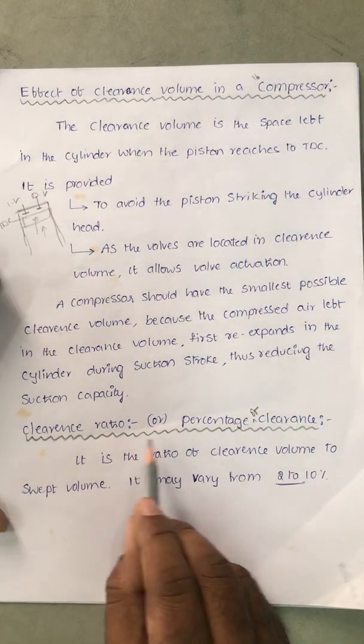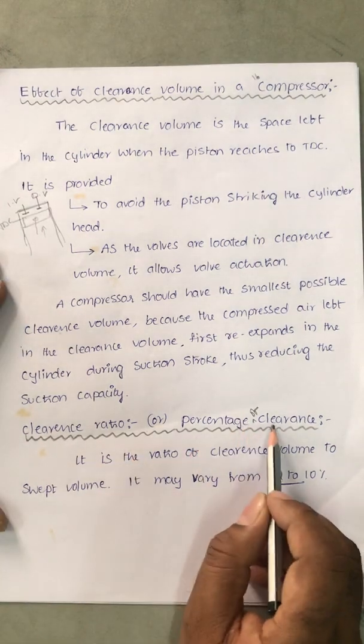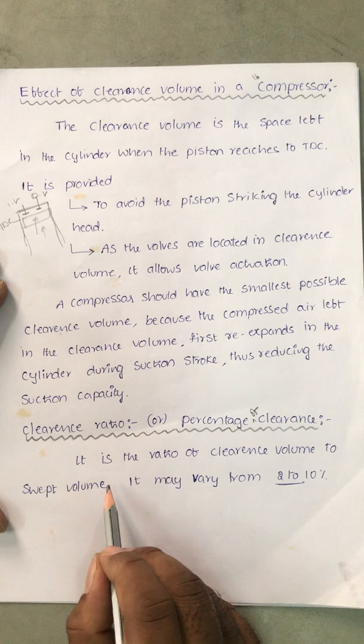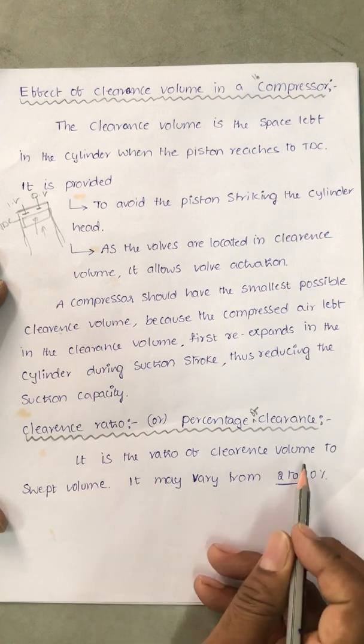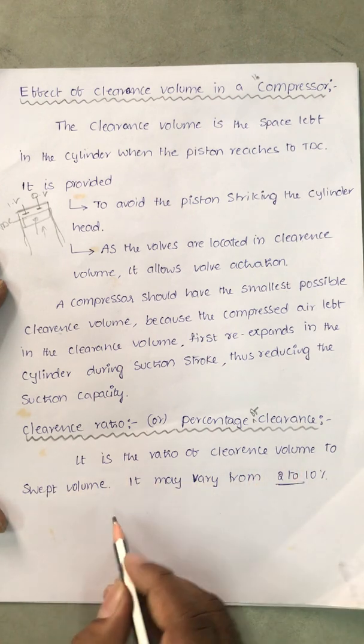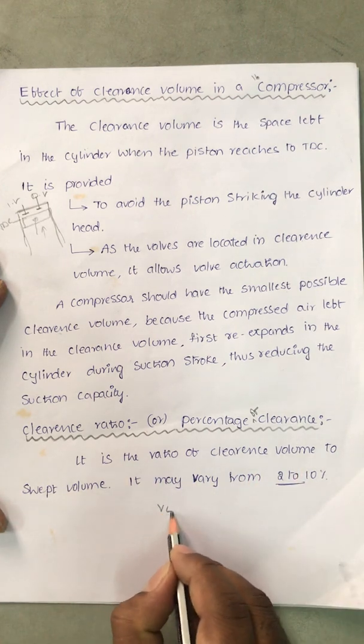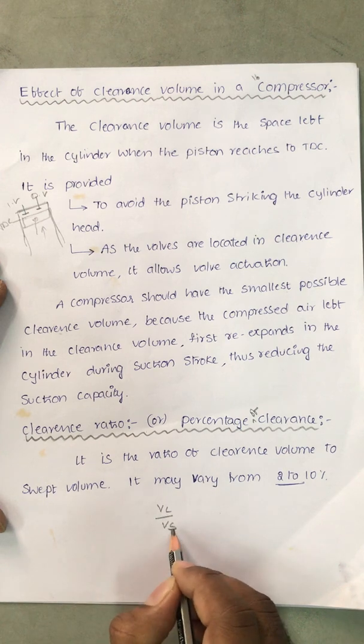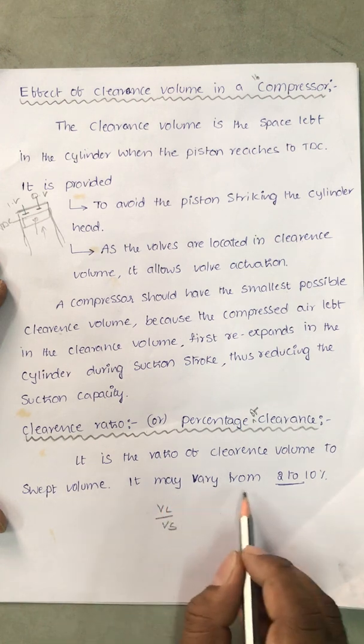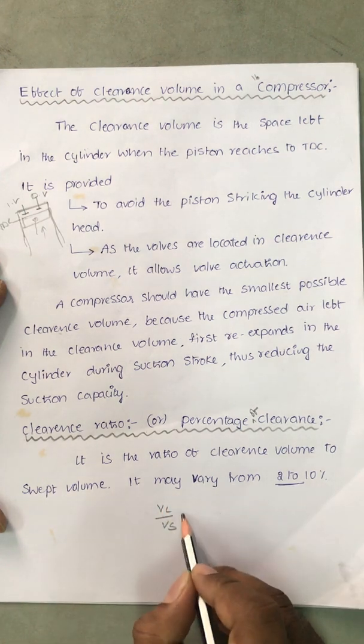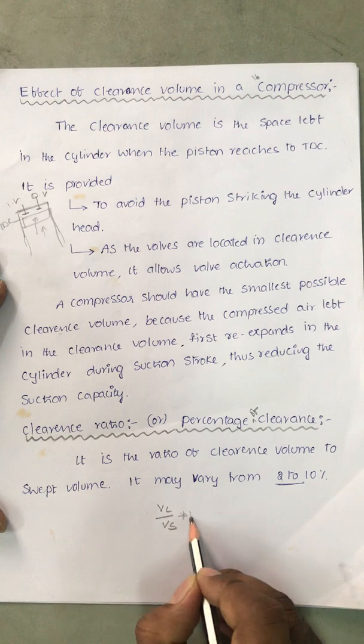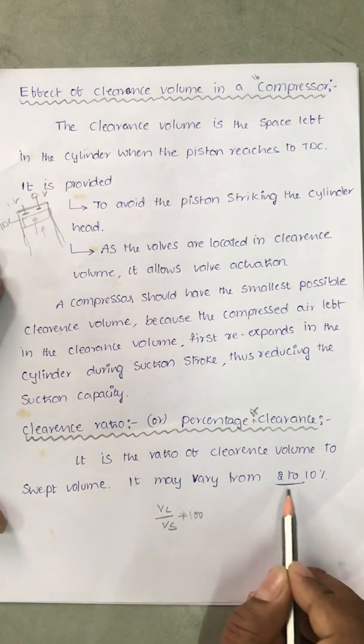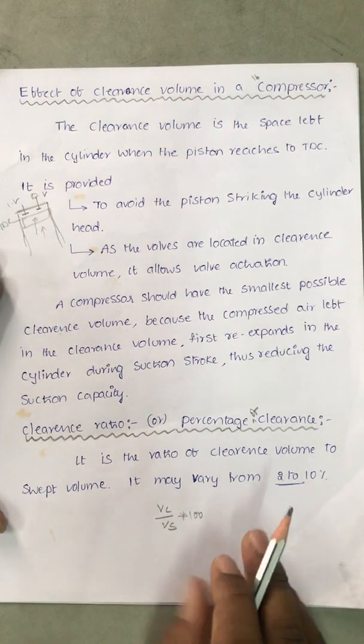The clearance ratio — also called percentage of clearance or clearance percentage — is the ratio of clearance volume to swept volume, that means Vc divided by Vs. It may vary from 8 to 10%.